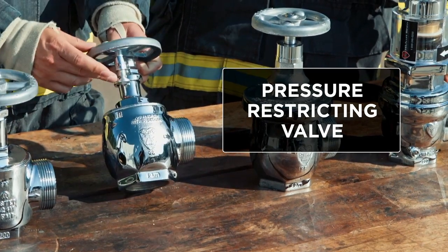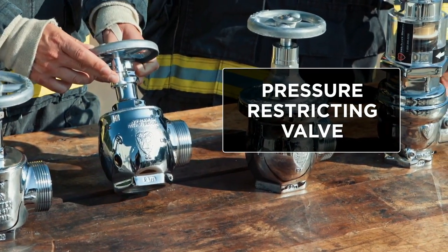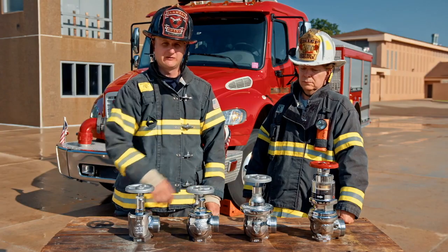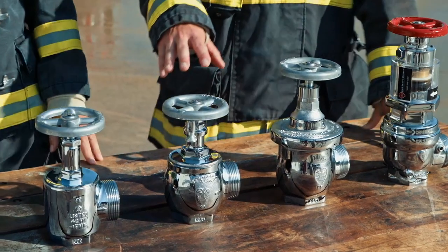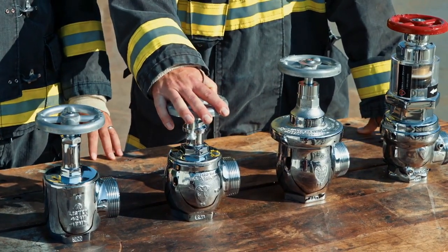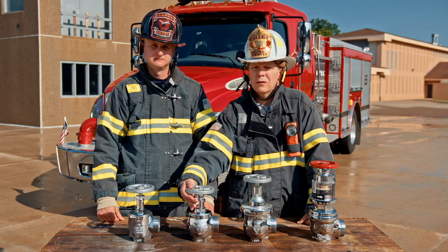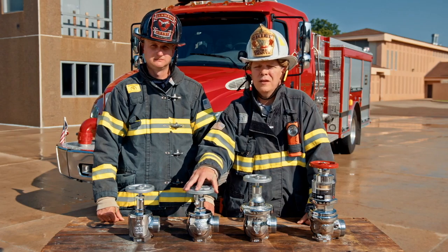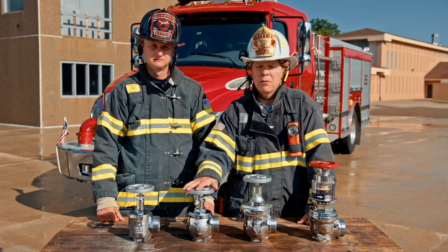The design of this type of valve is a device on the exterior that limits how far the valve can actually open. The pressure restricting valves complicate things just slightly for firefighters because there is an external device that does not allow firefighters to open this fully. That's how it restricts the pressure.